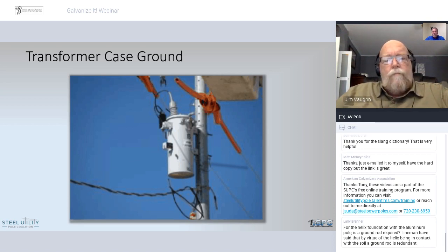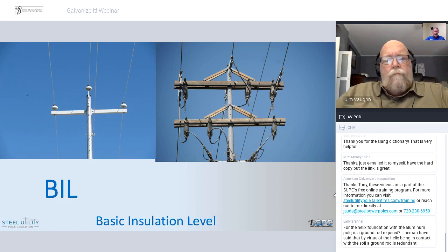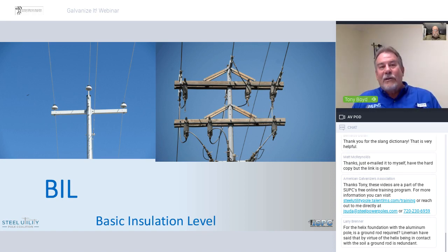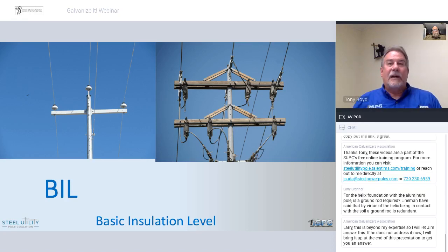Thank you, Jim. I'll skip a slide or two, kind of finish up, and just talk a little bit about our basic insulation levels. Of course, they need to be increased slightly for the steel poles. The basic insulation level is the relative measure of a structure's insulation to withstand overvoltage impulses. So we design a system with the insulators to withstand the voltage. Jim mentioned 15 kV, 15,000 volts. It may be 13,000 volts phase to phase. Some systems are 14,000 volts phase to phase. So the insulators are actually rated for a little bit larger voltage, and that's what the basic insulation level does. It allows for an overvoltage, such as a lightning strike or a transmission line maybe falling onto a distribution system.